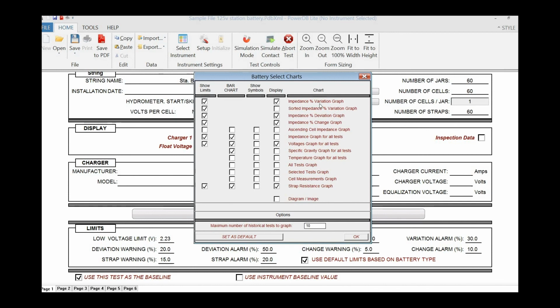Now, the charts I've chosen include the impedance variation graph, which compares each cell's impedance to the string average, the impedance deviation graph, which compares each cell's impedance to the baseline, the impedance change graph, which compares each cell's impedance to its previous test impedance value, the voltage graph, so I can view the float voltage of each cell, and the strap resistance graph, which will allow me to find which straps may need attention. I can view these as bar charts or line charts.